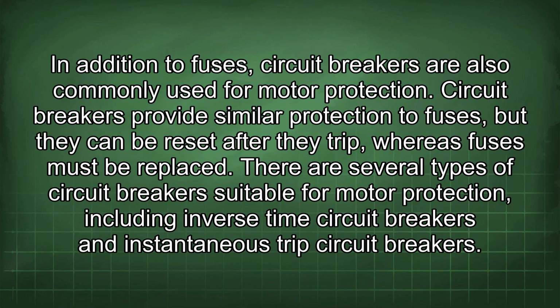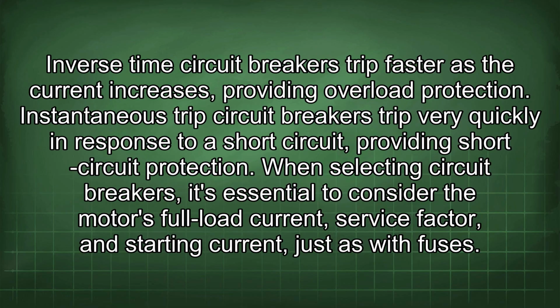In addition to fuses, circuit breakers are also commonly used for motor protection. Circuit breakers provide similar protection to fuses, but they can be reset after they trip, whereas fuses must be replaced. There are several types of circuit breakers suitable for motor protection, including inverse time circuit breakers and instantaneous trip circuit breakers. Inverse time circuit breakers trip faster as the current increases, providing overload protection. Instantaneous trip circuit breakers trip very quickly in response to a short circuit, providing short circuit protection.